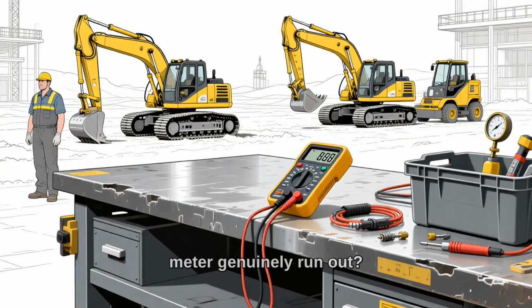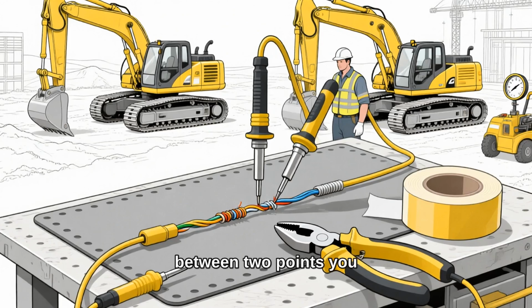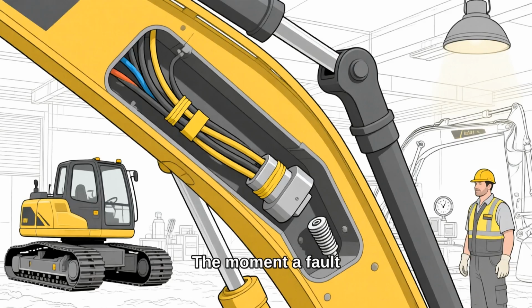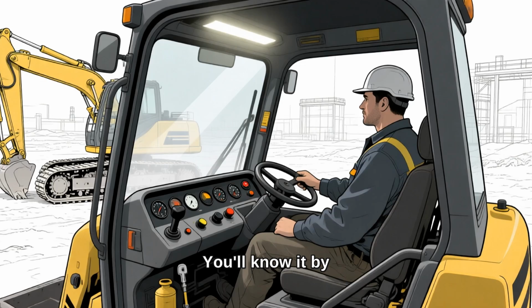So where does the meter genuinely run out? The line is sharper than most people expect. A meter tests one thing between 2 points you chose. It's only ever as smart as your guess. The moment a fault involves a shared path, a common ground, a splice feeding 4 circuits, guessing collapses. You'll know it by the symptom. 2 unrelated things quit together, and nothing on the machine connects them.